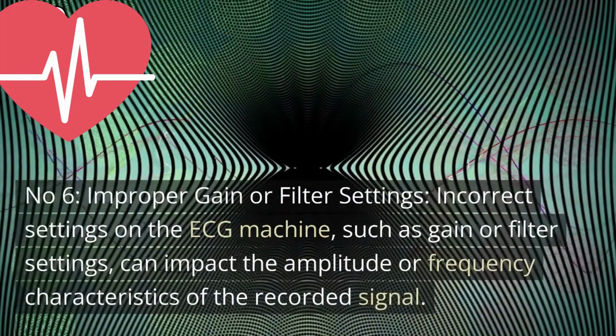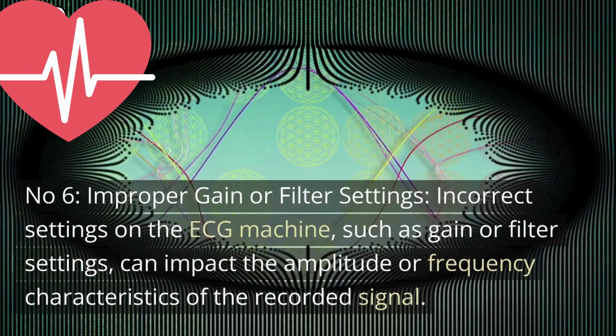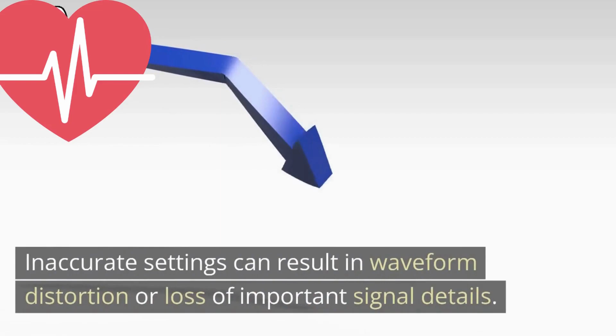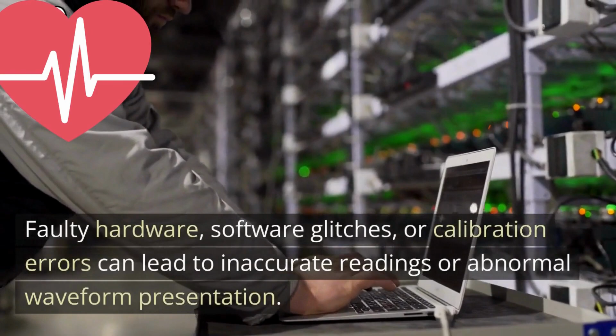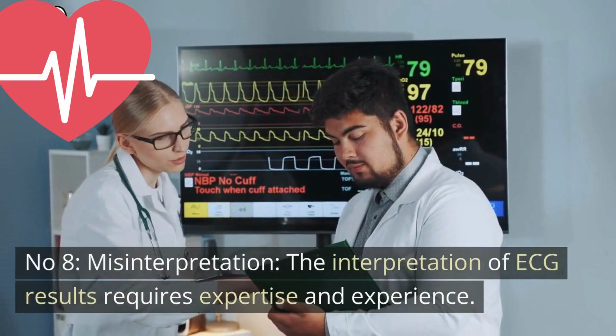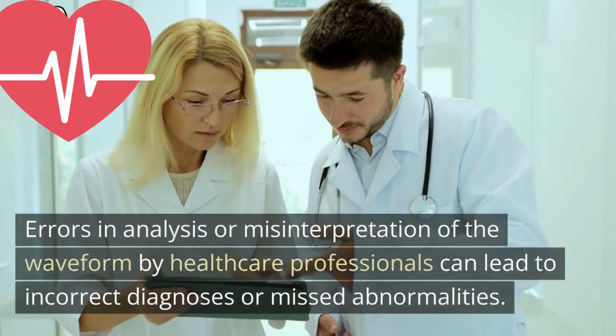Number 6. Improper gain or filter settings. Incorrect settings on the ECG machine, such as gain or filter settings, can impact the amplitude or frequency characteristics of the recorded signal. Inaccurate settings can result in waveform distortion or loss of important signal details. Number 7. Technical malfunctions. ECG machines are electronic devices and can experience technical malfunctions or calibration issues. Faulty hardware, software glitches, or calibration errors can lead to inaccurate readings or abnormal waveform presentation. Number 8. Misinterpretation. The interpretation of ECG results requires expertise and experience. Errors in analysis or misinterpretation of the waveform by healthcare professionals can lead to incorrect diagnoses or missed abnormalities.